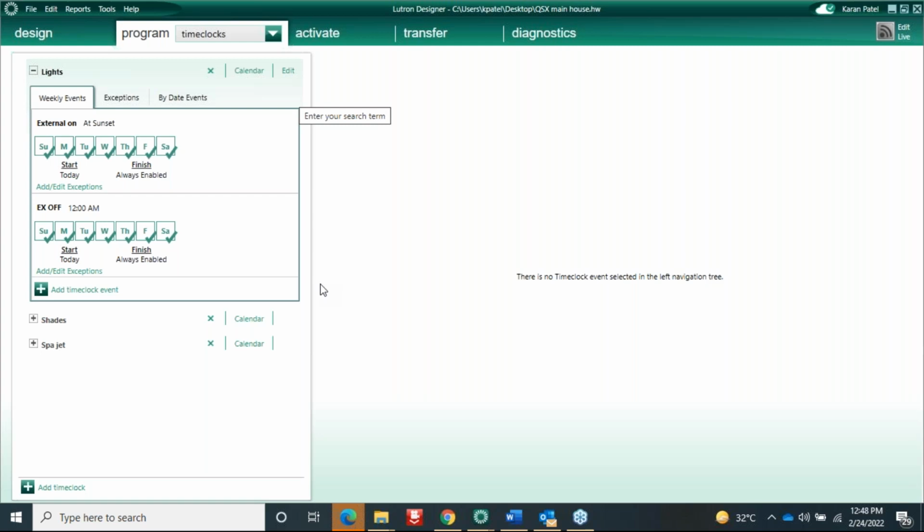So Lutron knows in India in 2021 what the sunset timing and sunrise timing are, and the accuracy is plus or minus 1 minute. That is the accuracy for the time clocks, and based on that we decide the sunset and sunrise. It is not based on climate changes, so if you have a sudden cloud or sudden rain the system will not be able to understand, but the sunset and sunrise timing will be tracked by that algorithm which is stored inside the processor.